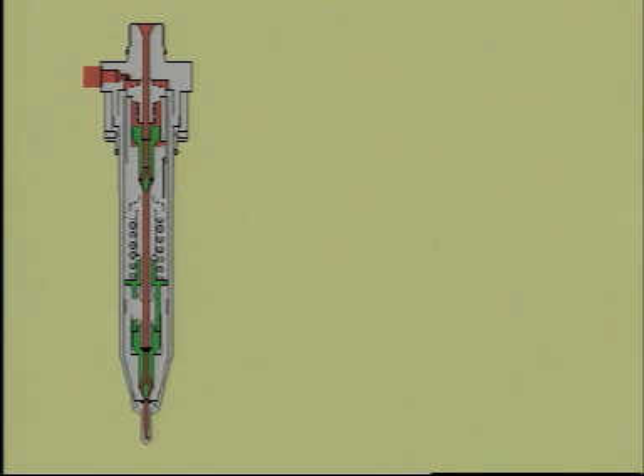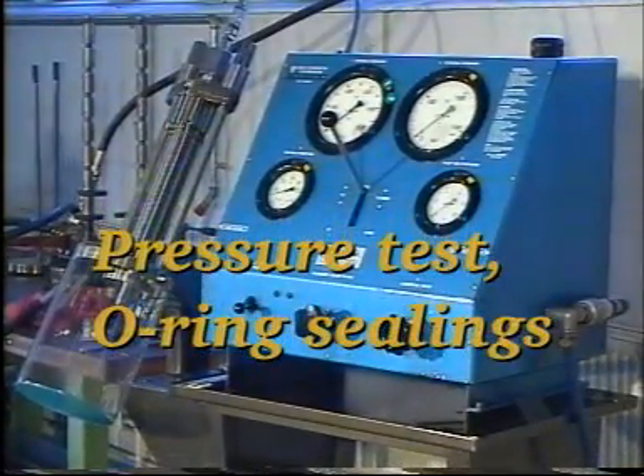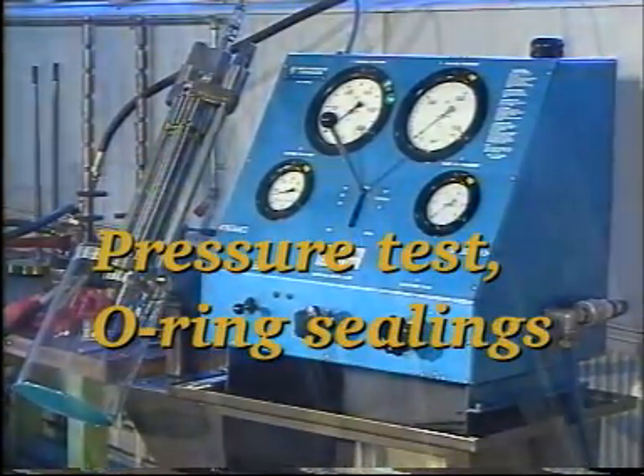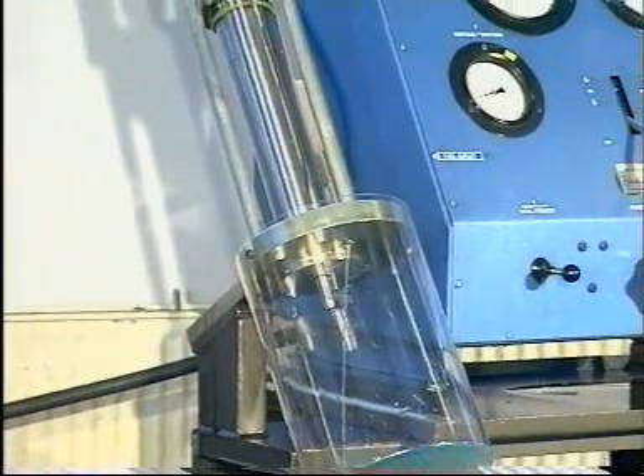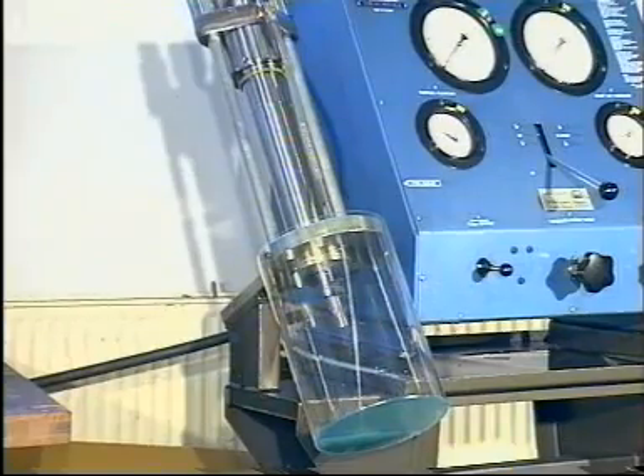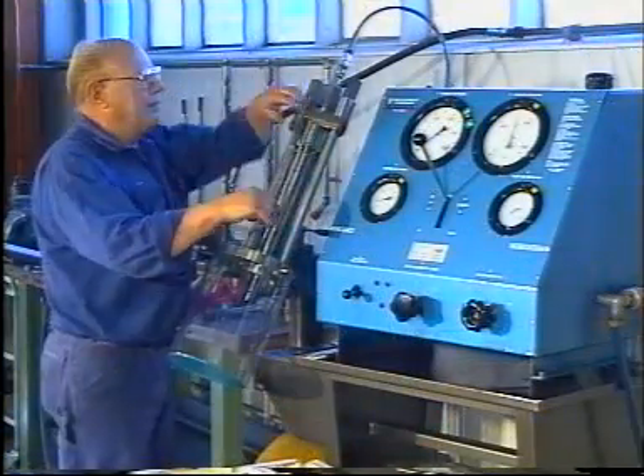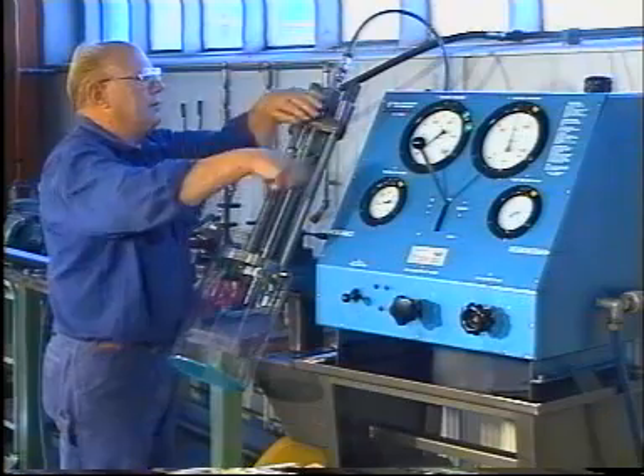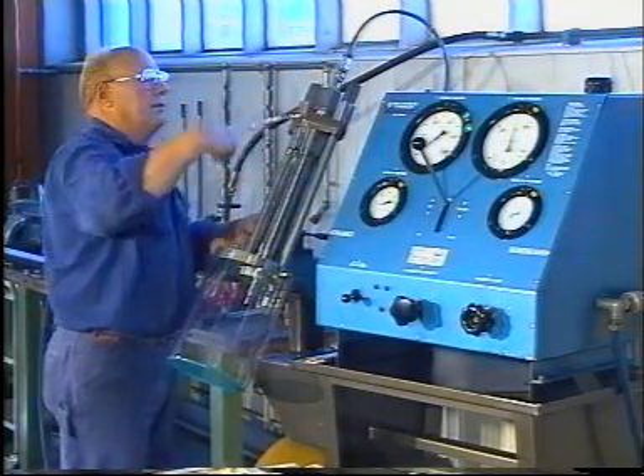If the quick pressure drop cannot be registered, the slide is sticking, or the hole is blocked, disassemble and examine the parts, replace if necessary. Slowly fill the valve by pumping at low pressure until fuel oil, without air bubbles, flows from the fuel oil return pipe. Remove the fuel oil return pipe and block the outlet hole with a gasket and a plug screw.